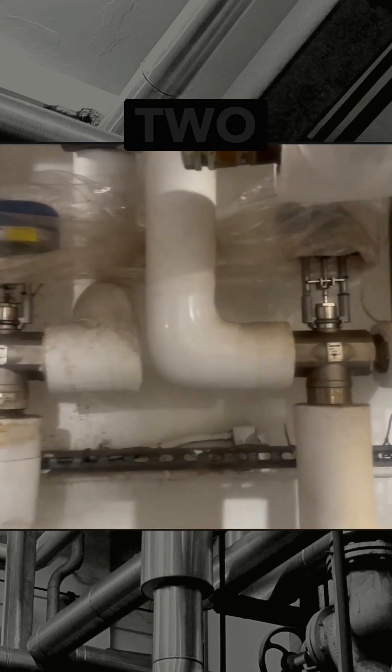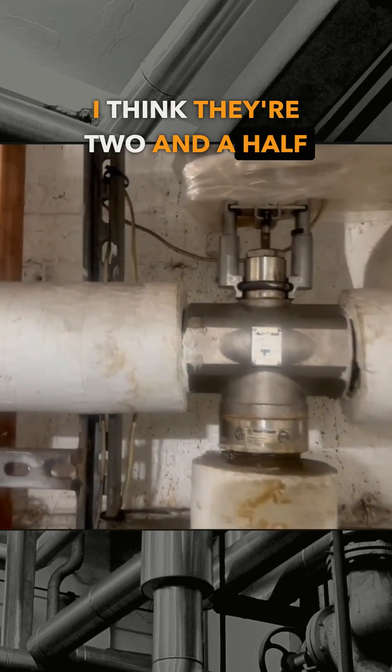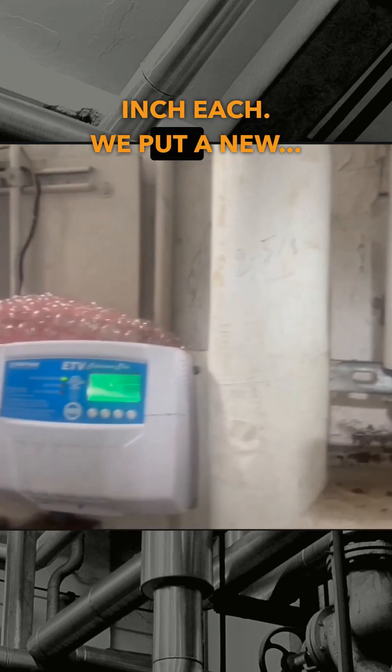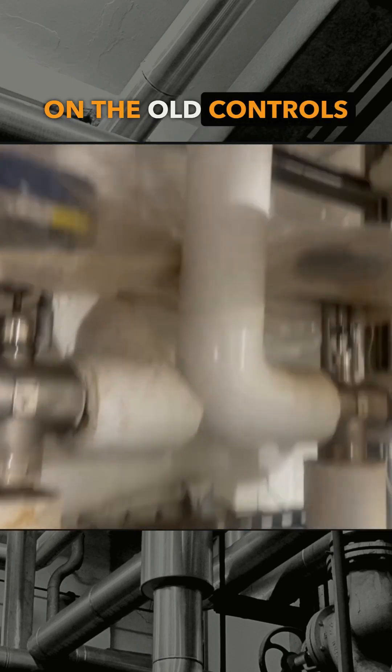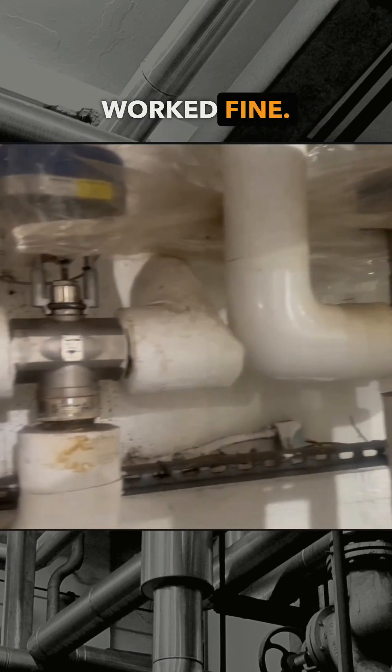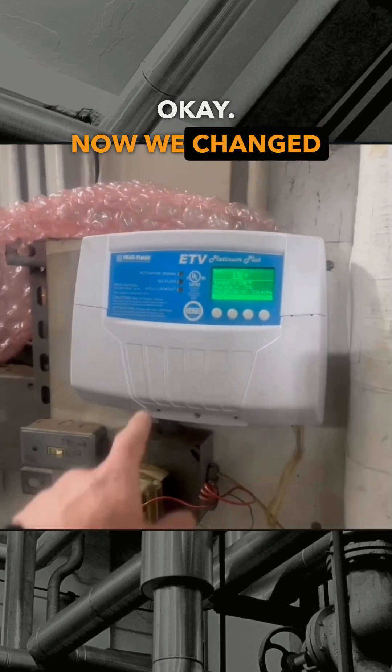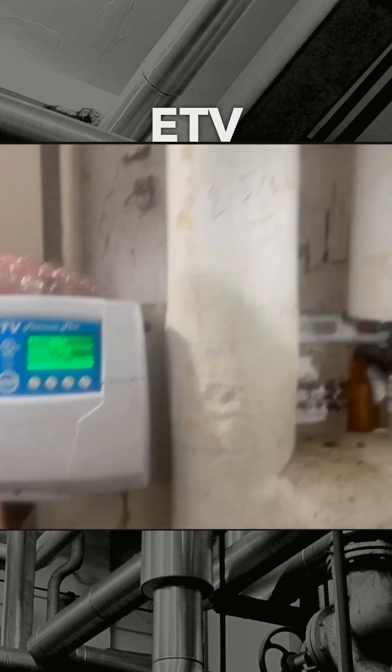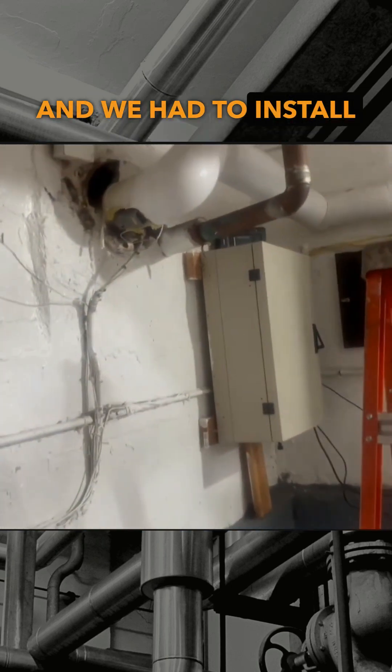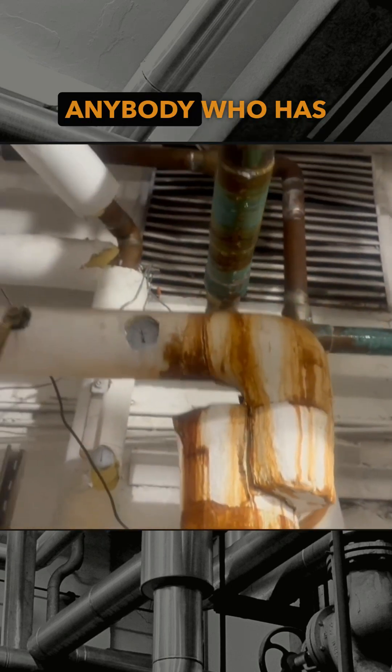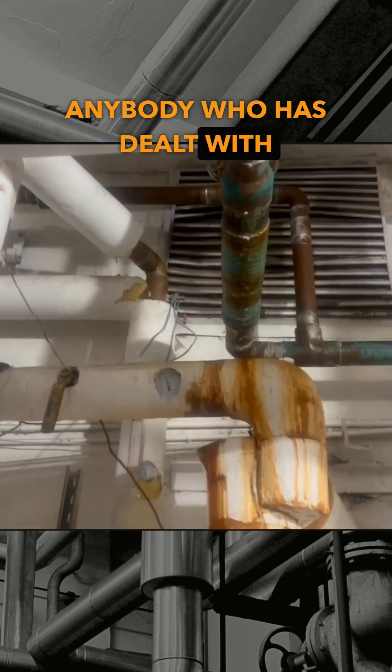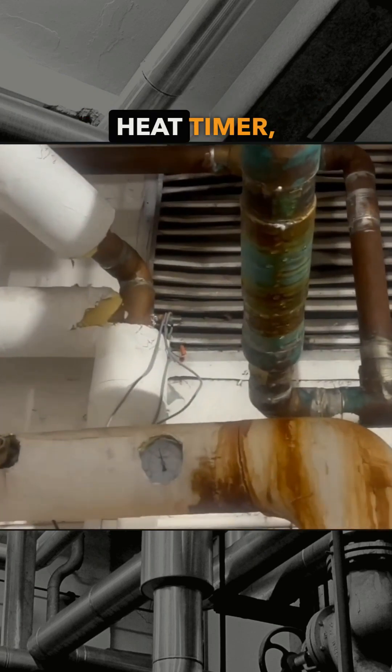So two valves, I think they're two and a half inch each. Here's the thing - on the old controls this would have worked fine, it was working okay. Now we changed it to ETV Platinum Plus and we had to install the newest sensor.